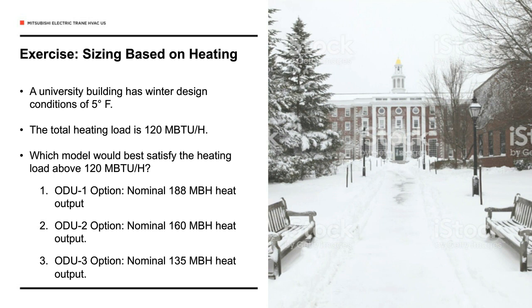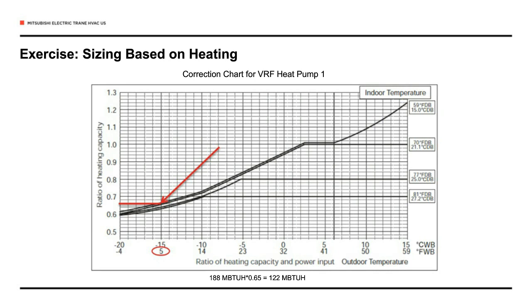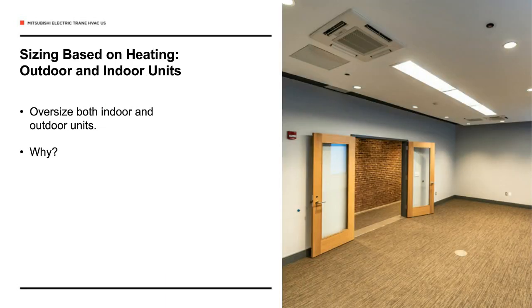Well, if we look at the heating derate charts, and like I said earlier, most people are going to use the software to determine this, not actually pull out the manuals, but there still may be some people that would do it this way. If we look at 5 degrees, we can see that the heating output goes down as we go to the left, in other words, it's getting less as we get colder. We have a heating derate at that temperature of about 0.65. So our nominal heating output at 47 times 0.65 gives us what that unit will do at 5 degrees above zero. And if we do the math, we'll see that that ends up being the largest unit shown, the one that was 188 MBH. 188 times 0.65 equals approximately 120 MBH.